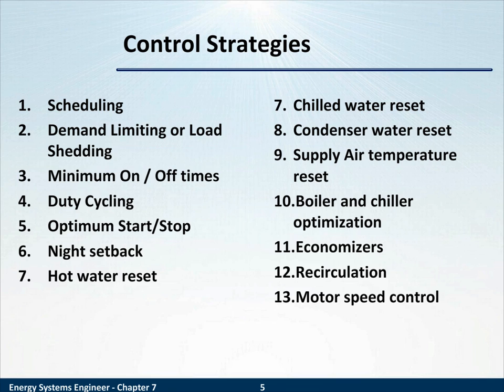So if you start the air conditioner at 6 a.m. so that it'll be cool by 7:30 a.m., you can cool your building down faster if you shut off outside air, fresh air makeup. You couldn't do it with people in the building, but without people in the building, recirculation says shut down the exhaust and the outside air for a period so that you can cool or heat your building faster. And then, of course, motor speed control. We've talked about that in the electrical systems and motor section.